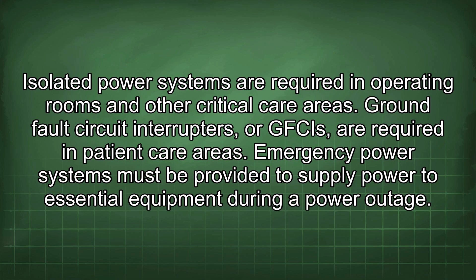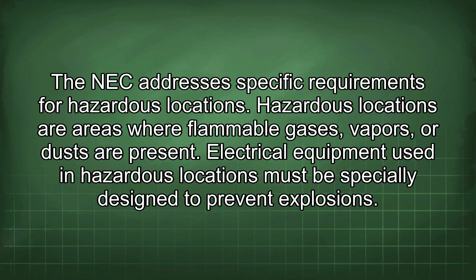The NEC addresses specific requirements for hazardous locations. Hazardous locations are areas where flammable gases, vapors, or dusts are present. Electrical equipment used in hazardous locations must be specially designed to prevent explosions. Different classes and divisions of hazardous locations are defined in the NEC.